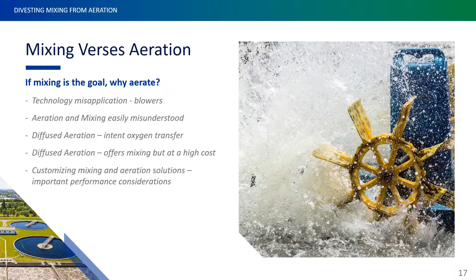Mixing is an important element of aeration, but excessive aeration comes with significant downsides as well: more energy use, oversizing of blowers, misapplication using air for mixing. It creates operational issues, fouling, plugging, foaming, filamentous bulking, all issues that operations has to manage, and they result from inaccurate aeration, which results in a high DO or whatever it might be.